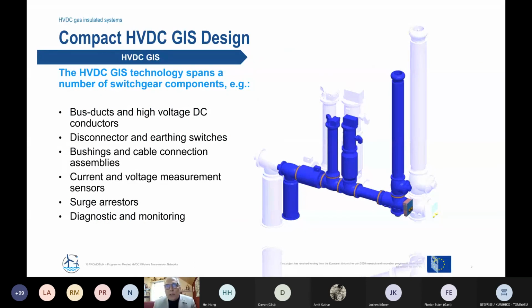Looking at the components we need for an HVDC GIS, that is very similar to an AC GIS. You can see here one picture of the typical components, which is very similar from the different manufacturers of an HVDC GIS. Starting from the right side, we have a connection between GIS and air, so the bushing from gas to air. Going from right to left, we have a disconnector and earthing switches, connecting elements, surge arrestor, and voltage and current measurement devices. Normally for a DC GIS, an RC divider is used for voltage measurement, and the zero flux principle is used for current measurement. On the left side, you can see a cable termination, so a connection from a GIS directly to an HVDC cable. Moreover, we also need diagnostic and monitoring tools very similar to an AC GIS.